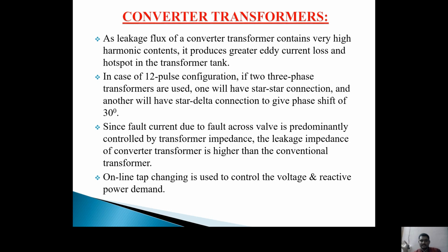Since the fault current due to a fault across the valve is predominantly controlled by transformer impedance, the leakage impedance of a converter transformer is higher than that of a conventional transformer.